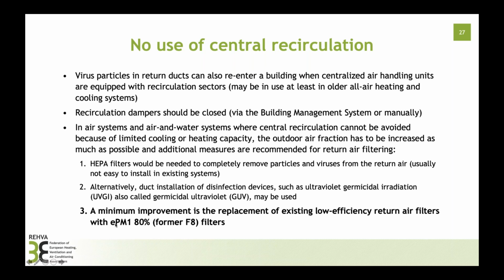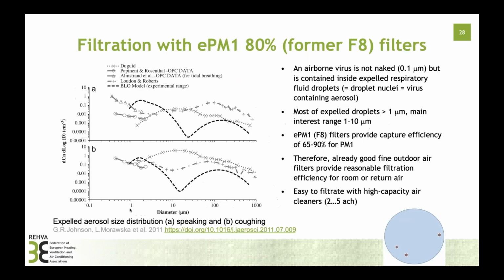So this means filter efficiency of 80% or more for particles smaller than 1 micrometer, so former F8 filters according to the European classification. And that's perhaps the most common option that has been applied in practice. So, outdoor air rate increased reasonably, so it's at least 50%, and then installing better filters on the return air side.